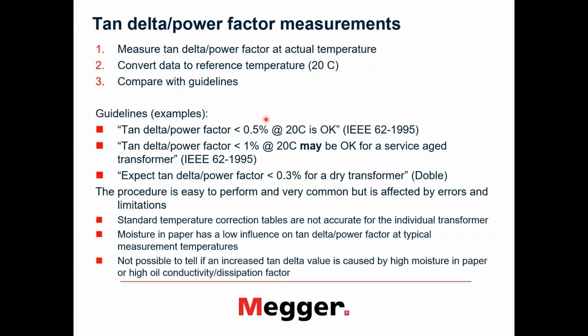So this procedure is normally done whenever you do diagnostic tests, and it's easy, but it's affected by errors due to temperature correction tables, which are not accurate; you cannot use the same table for new transformers and aged transformers. They will be different. And at typical measurement temperatures like 20-30 degrees, moisture in paper will actually have quite a low influence on the power factor at power frequency. And also it's not possible to tell if, for example, increased tangent delta is related to high moisture content in paper or high oil conductivity, which can also happen.